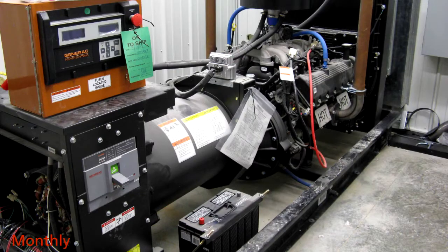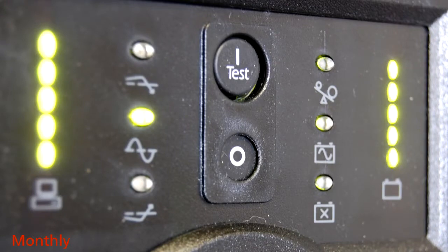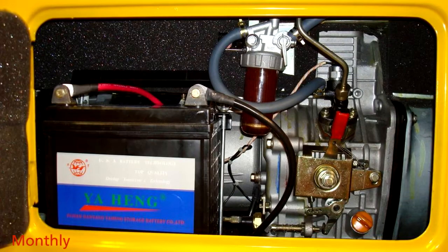On a monthly basis, your site staff should check pilot lights on self-contained emergency power units to ensure proper operation. Power units must be inspected to ensure that terminal connections are clean, lubricated, and free of corrosion. Terminal clamps are clean and tight, and the battery surface is clean and dry.